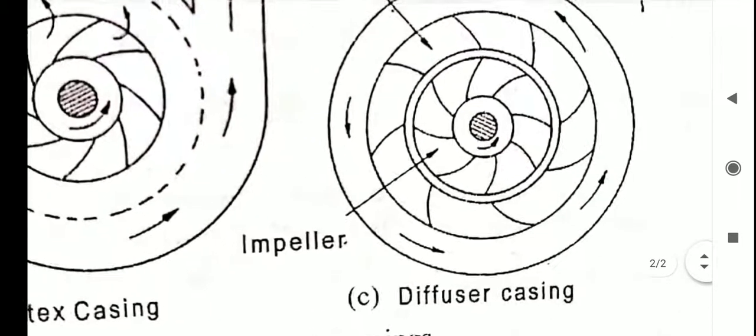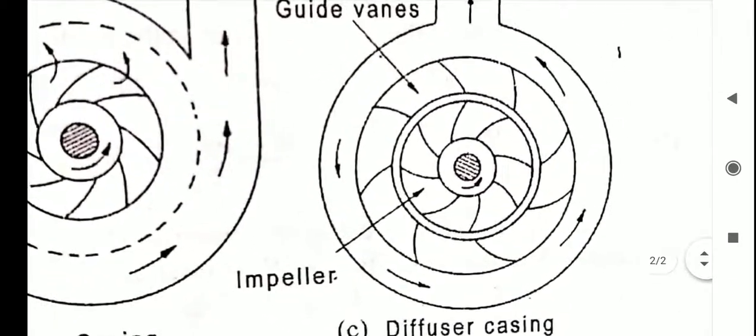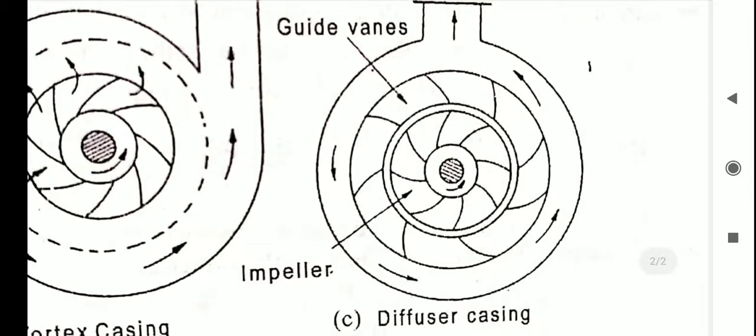The water from the impeller enters the guide blades without shock and flows through the increased area of flow of the guide vanes. As the water passes through the increased area of the guide vanes, the velocity is further reduced and hence more pressure recovery is achieved.